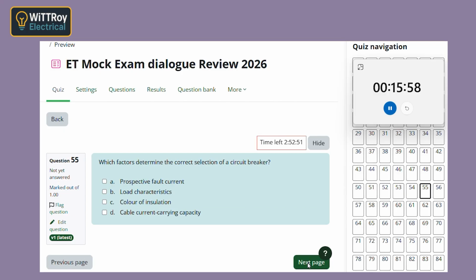Question 55. What determines correct selection of a circuit breaker? Prospective fault current and cable current capacity? Yes, and also load characteristics. Let's unpack that. Prospective fault current matters because the breaker must be able to safely interrupt the maximum fault current that could occur at that point. So if the fault current is higher than the breaker can handle, that's dangerous.